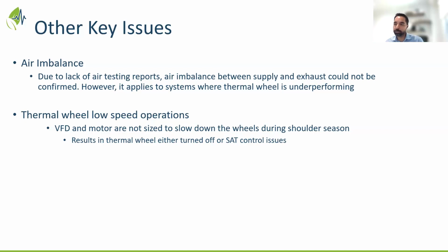And I think the best thing is to spec these correctly from the design point, from the starting point, because that's generally not done at the design stages. This is not typical of other air handling units. This is very specific to the thermal wheels. So that design specification has to be adjusted to make sure you get these low RPM operations enabled on the wheels.